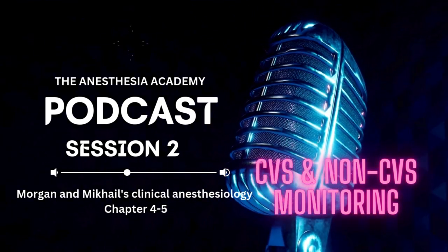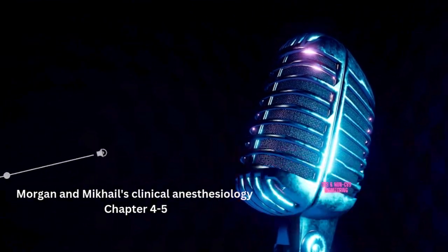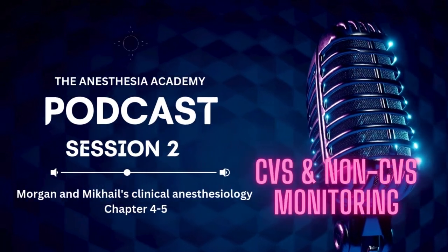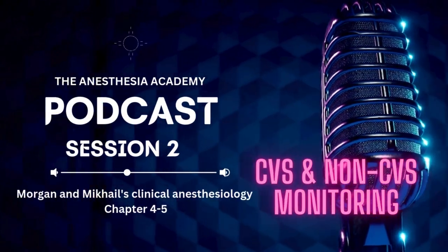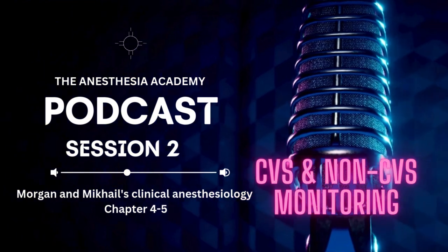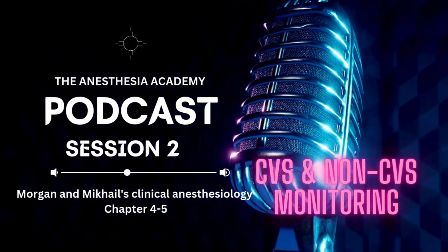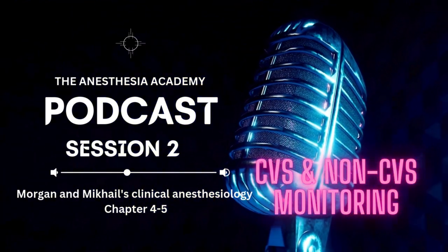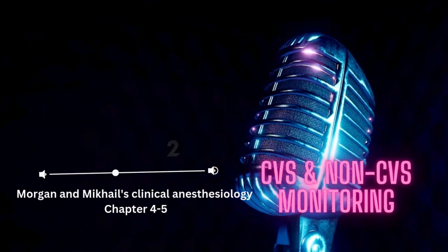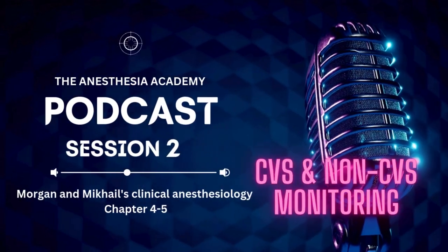I know we have different types of capnographs, non-diverting and diverting. What are the key differences? Non-diverting, or mainstream, have a sensor directly in the airway. Fast, accurate readings, but they're bulkier, often more expensive. Got it. And the diverting, or sidestream? They sample a bit of gas from the circuit. More compact, but can be affected by things like water condensation.